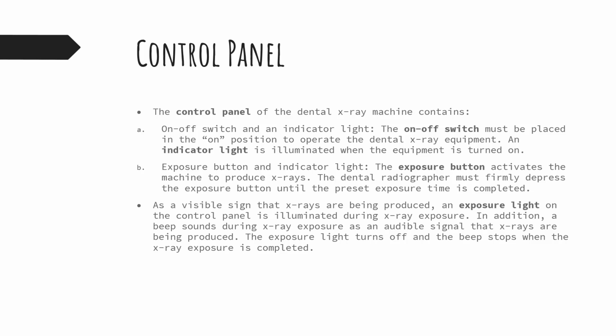So, for example, if it is set at 0.1 seconds, when that time elapses, even though you are still pressing, no further X-rays are produced. There's also an audible sound heard in addition to the indicator light, indicating that the exposure is completed.